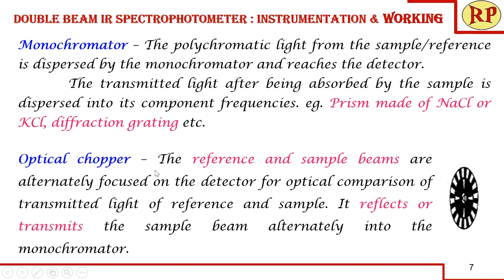The optical chopper alternately focuses the reference and sample beams on the detector for optical comparison of the transmitted light. If the sample beam is reflected, the reference beam is transmitted, and the other way around.